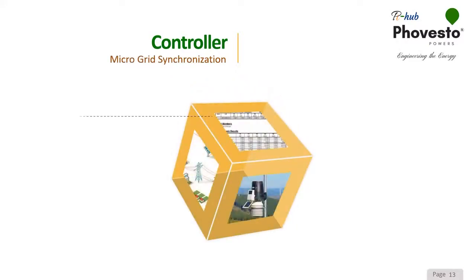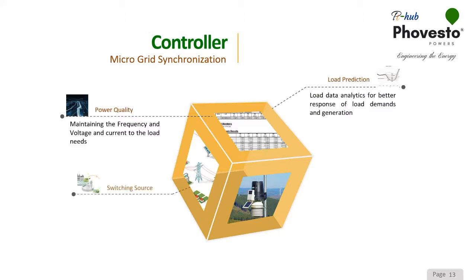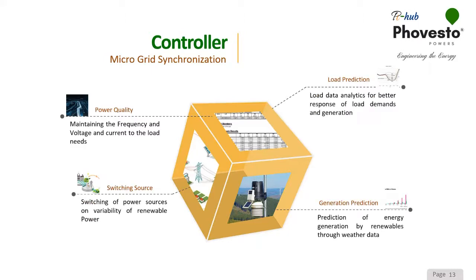The controller is the key component in any microgrid. It predicts the load when a new load is added. When we turn on a switch, there is added energy which needs to be met by the microgrid. This data is collected from the utility side and communicated back to the grid. It looks for a source, for example, whether a renewable can address this load. If the renewable cannot address the load, it checks the energy storage system provided for instant response. And if the energy storage is not enough, it goes to a reliable fossil power source and gives a command to ramp up to address the need. That is the kind of philosophy the controller works on.